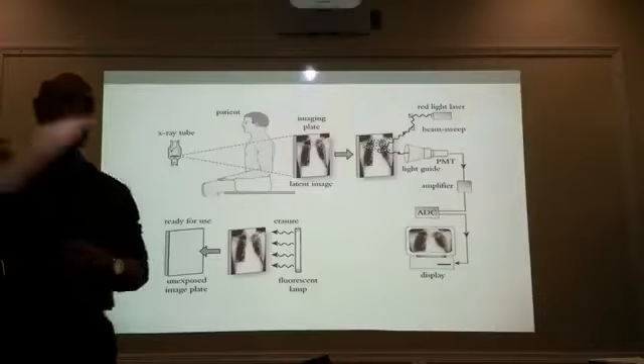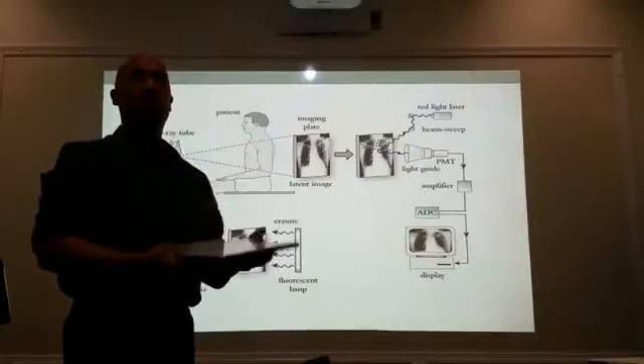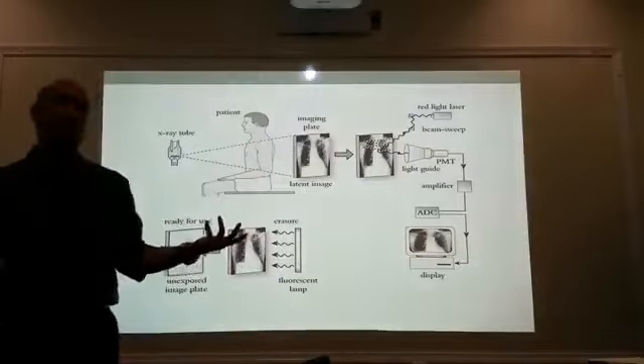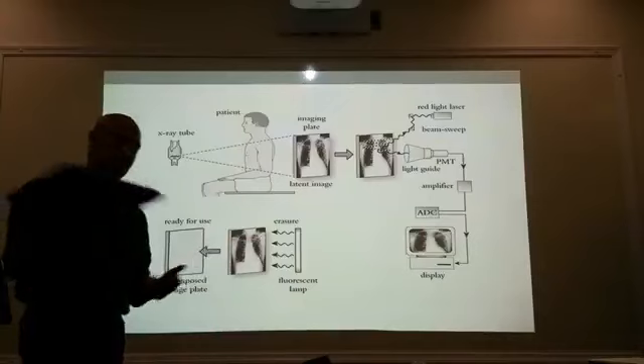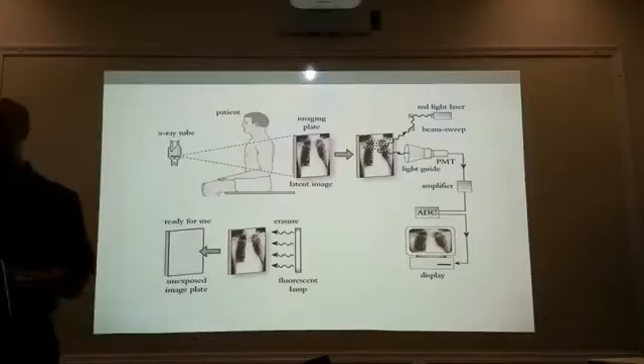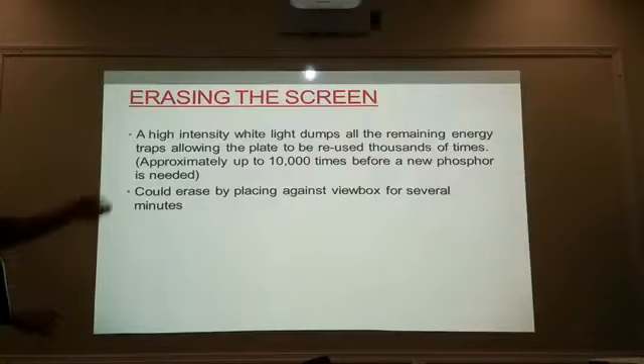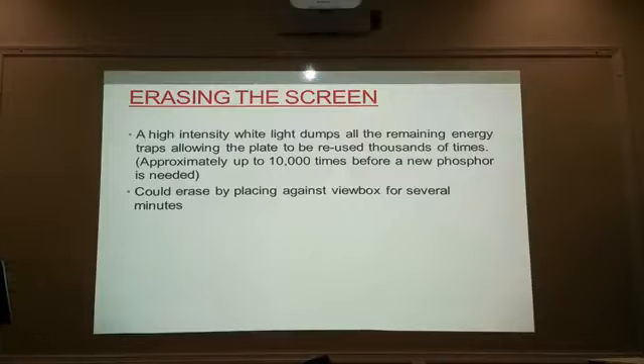Once it is erased, it puts it back into the cassette. We take our cassette out of the reader and it's ready to be used again — less than 20 seconds is all it takes for the whole process. The high-intensity white light dumps all the remaining energy, allowing the plate to be reused thousands of times over.